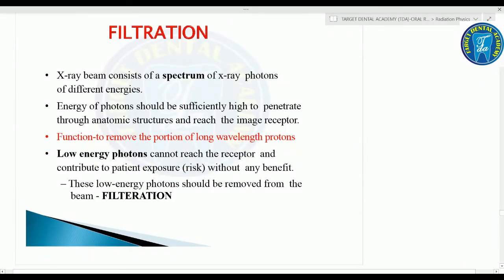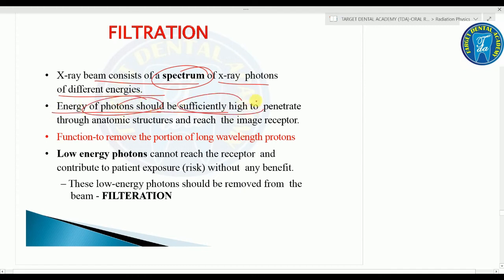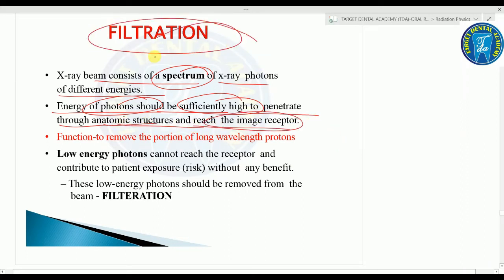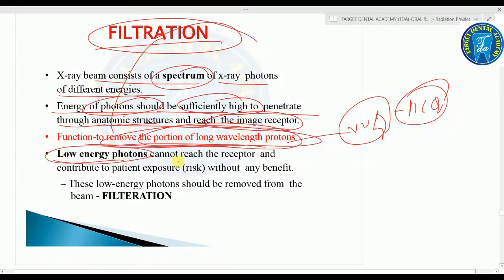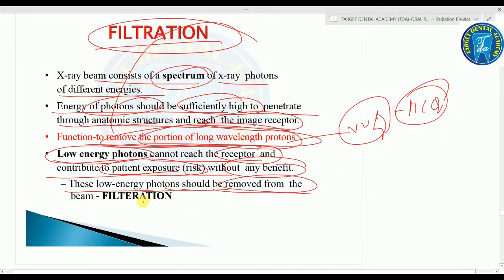Regarding filtration: the X-ray beam consists of a spectrum of X-ray photons of different energies. Photon energy should be sufficiently high to penetrate anatomic structures and reach the image receptor. The function of filtration is to remove the portion of long-wavelength, low-energy photons that cannot reach the receptor but contribute to patient exposure without any benefit.